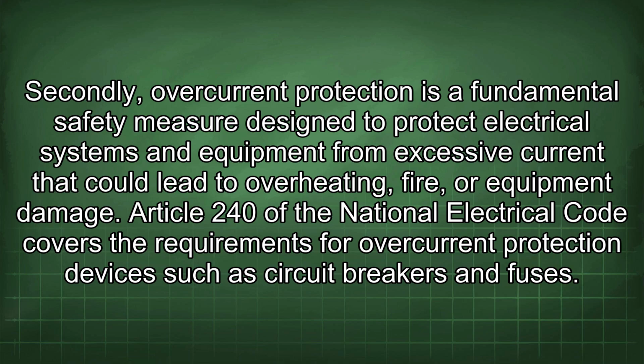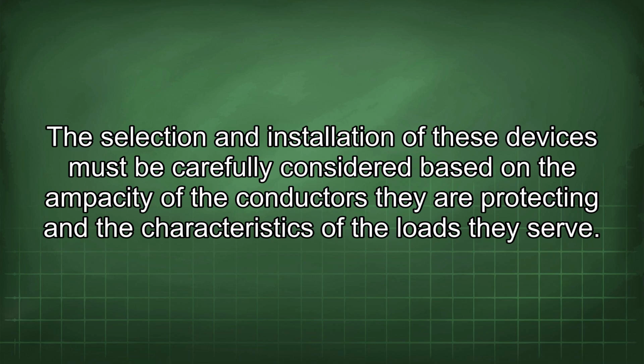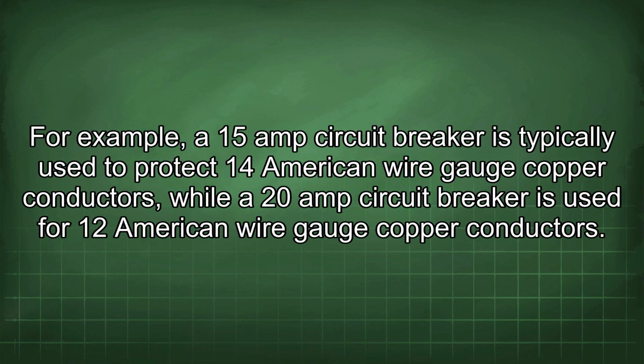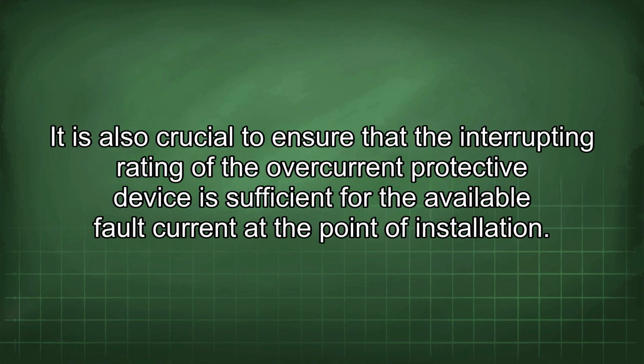Secondly, overcurrent protection is a fundamental safety measure designed to protect electrical systems and equipment from excessive current that could lead to overheating, fire, or equipment damage. Article 240 of the National Electrical Code covers the requirements for overcurrent protection devices such as circuit breakers and fuses. The selection and installation of these devices must be carefully considered based on the ampacity of the conductors they are protecting and the characteristics of the loads they serve. For example, a 15-amp circuit breaker is typically used to protect 14 American wire gauge copper conductors, while a 20-amp circuit breaker is used for 12 American wire gauge copper conductors. It is also crucial to ensure that the interrupting rating of the overcurrent protective device is sufficient for the available fault current at the point of installation.